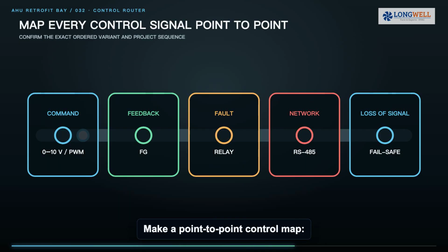Make a point-to-point control map: run command, speed feedback, fault relay, network address, and loss of signal behavior. The example LWBE3G450 sheet lists 0 to 10 volt, PWM, and RS485 options, but the exact ordered variant and project sequence still have to be confirmed. Test minimum speed, stop, restart and fail-safe behavior before handover.